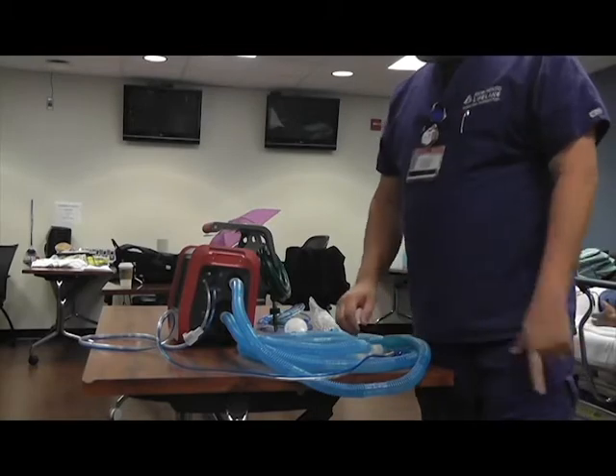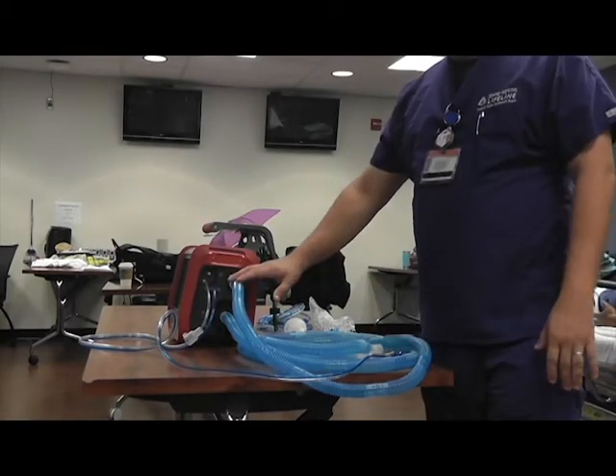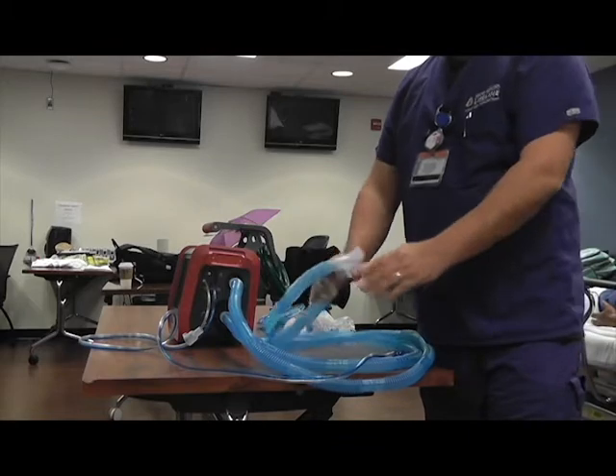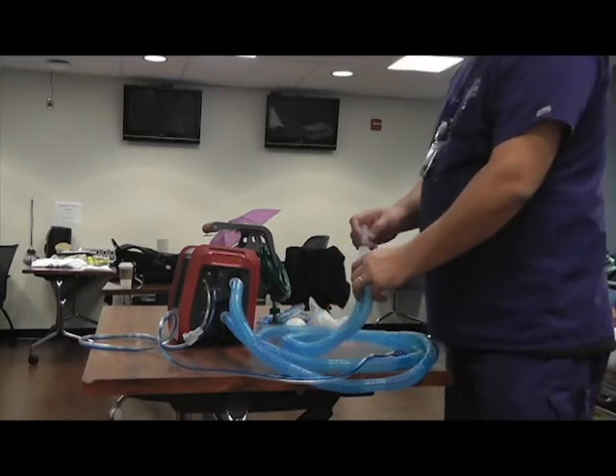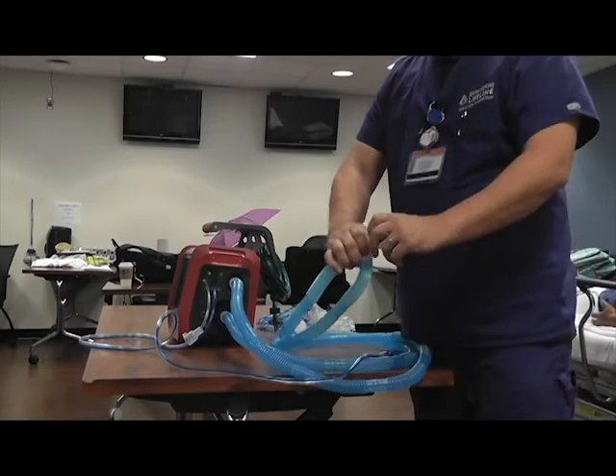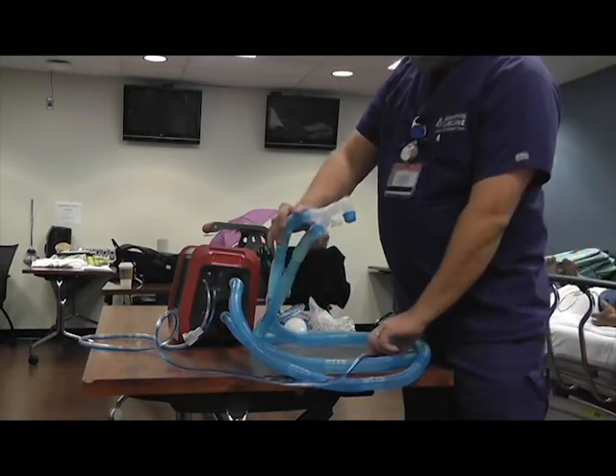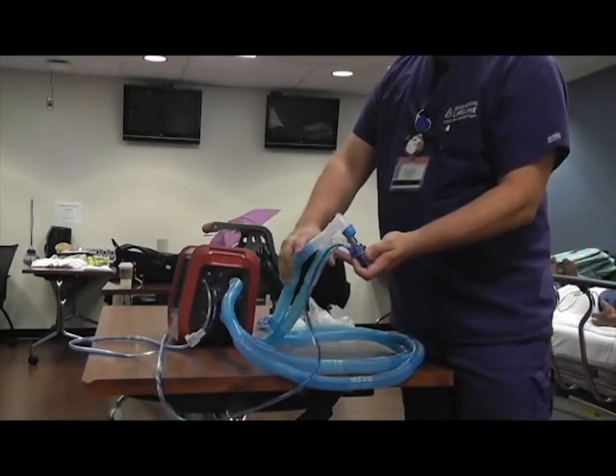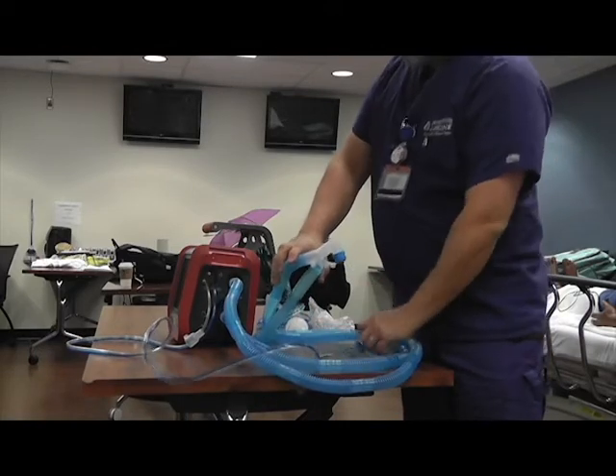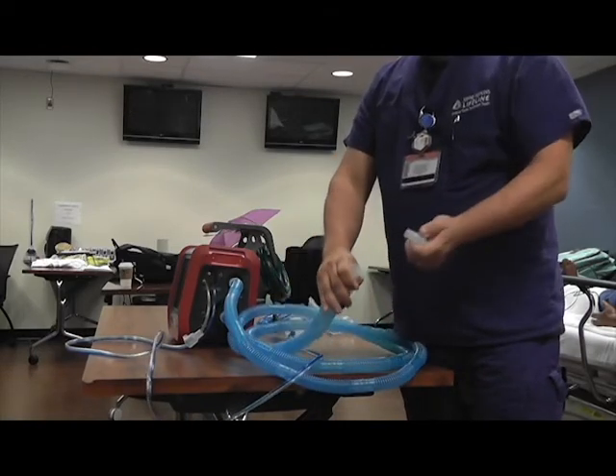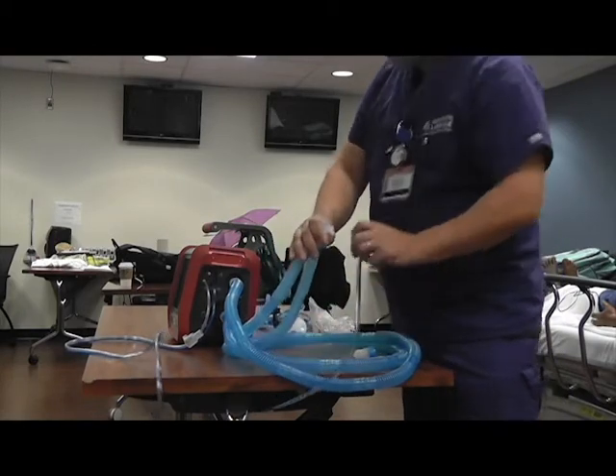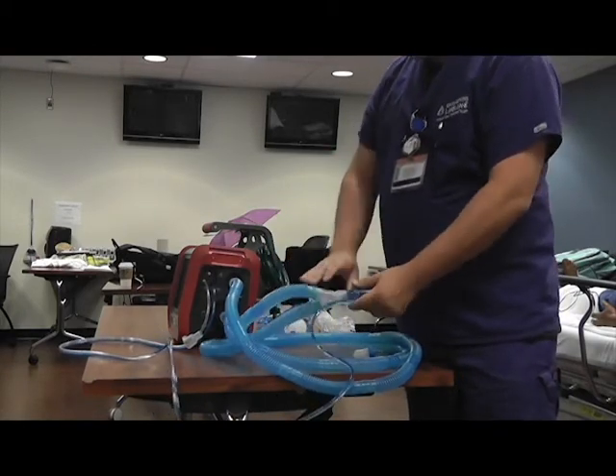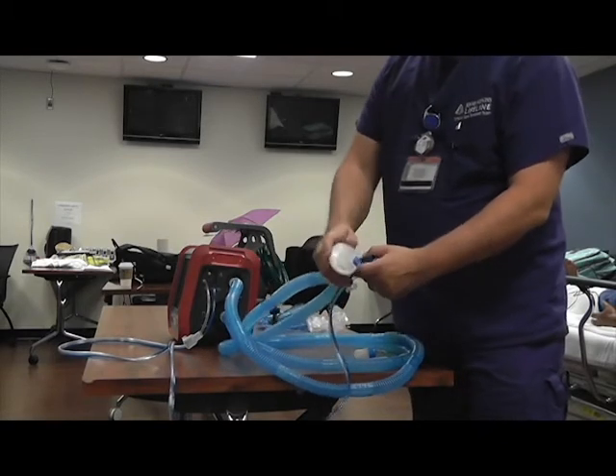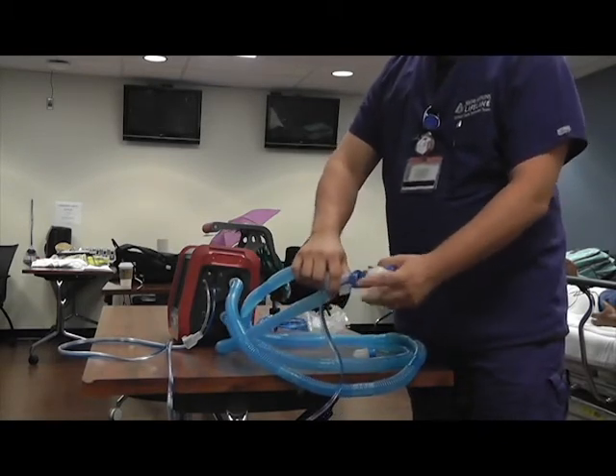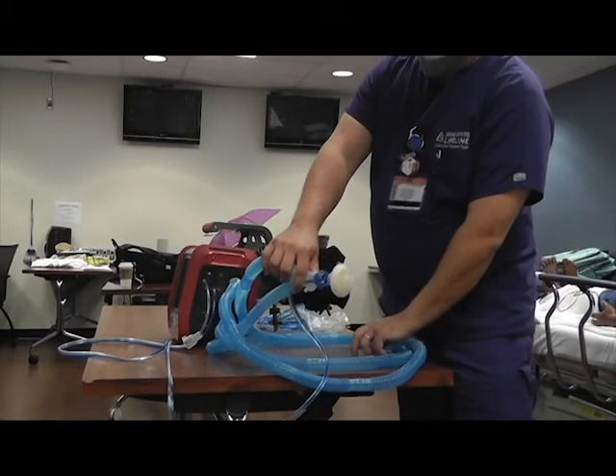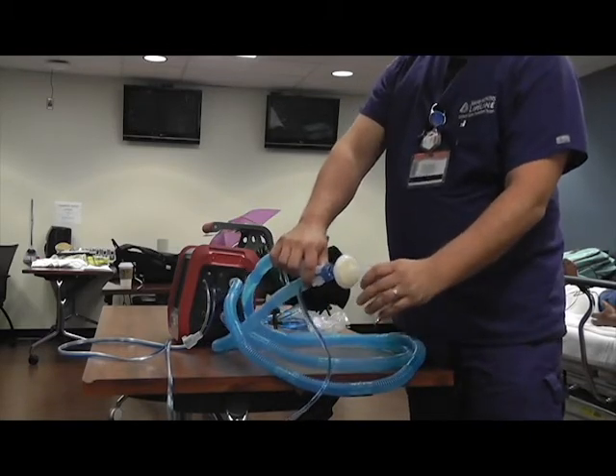Okay guys, I just wanted to show you an alternative way to set up this vent circuit, especially on the Y end where you connect the circuit to the patient. This is how the tubing is going to come, and the way Sam showed you is by putting the flow sensor on the bottom of this. An alternative way that you can do it is this elbow comes off, so you can take that off and you can place your flow sensor here, and then you can place your HME either in front of or behind the flow sensor, and then you can place the elbow back on.